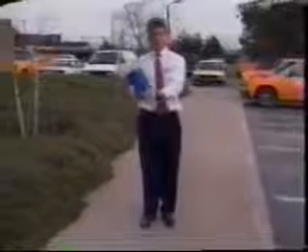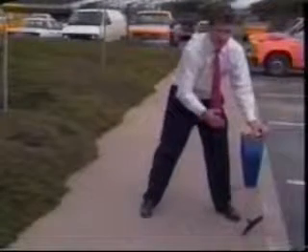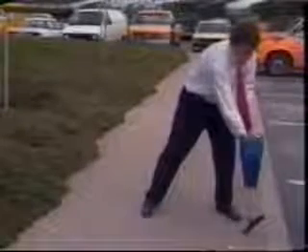Now to get depth, what you'd like to do is, it's notched at 45 degrees at the end of the knuckle here. I'll bring it up to a full tone. And again, we'll pull it away perpendicular to the utility, and we're looking for a null point. And again, the definition of a null is full, full, full, and cut out.